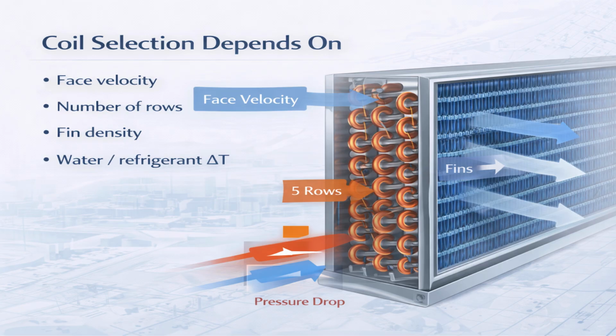If face velocity is too high, air passes over the coil too quickly. This increases the pressure drop and can lead to moisture carryover, where condensate is pulled back into the airstream instead of draining properly. On the other hand, simply increasing the number of rows is not always the solution. More rows increase airside resistance, raise fan power requirements, and can significantly increase noise levels.